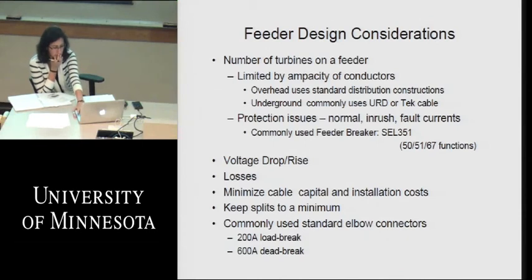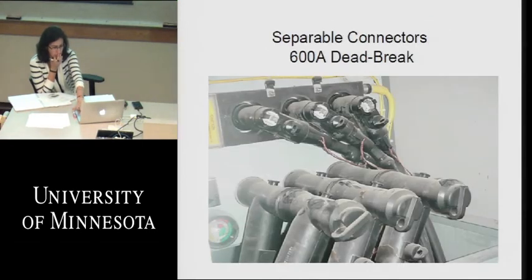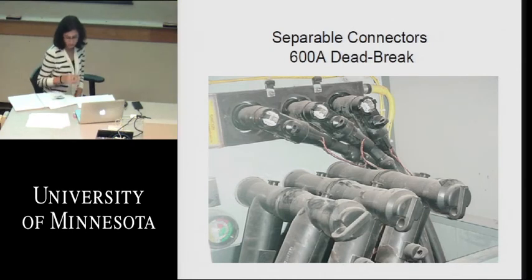It's kind of what they look like in the switchgear at the bottom of the wind turbine for one that has a transformer up on top. The top row of black ones are from the wind turbine itself. They go through basically a big SF6 breaker, and then it goes output on those two rows on the bottom that are piggybacked together. And that's a very conventional way we do that in the United States. Next slide.